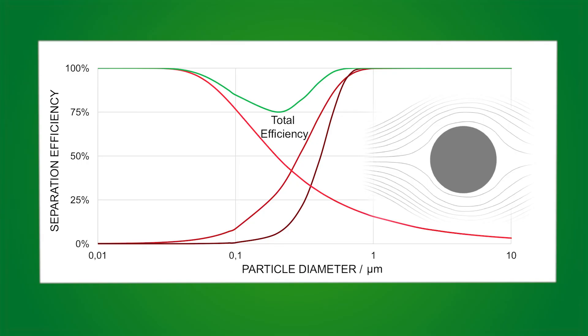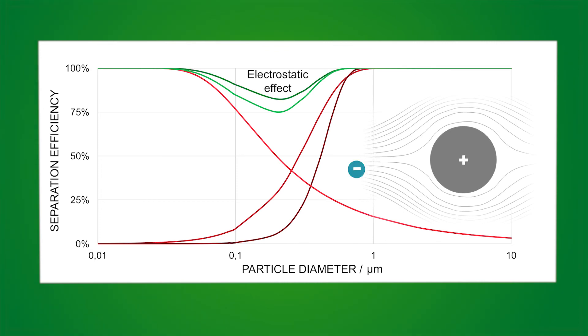If we sum up all these curves we can get the whole separation curve of a filter media. As you can see, there is a depression at the particle range of 0.3 micrometers, which is usually called the most penetrating particle point. This leads us to the last filtration mechanism, the electrostatic effect. For example, non-woven media can be charged, and these charged fibers can attract charged particles and therefore enhance the particle filtration in the range of 0.3 micrometers and elevate the point of most particle penetration.